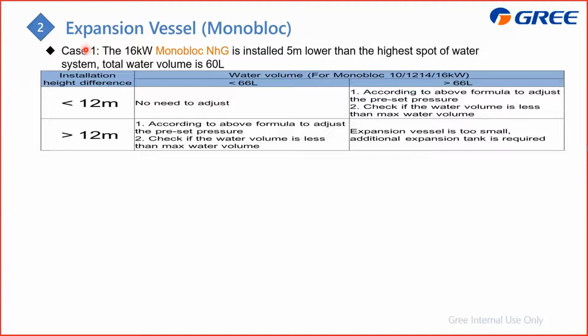So here is the detailed example. Case 1 is if you install a 16 kilowatt monoblock, and the water system is 5 meters lower than the highest spot of the water system, which means the outdoor unit is 5 meters lower than the highest point, and the total water volume is 60. According to this, you can find that if it is less than 66, which is this case, there is no need to install the preset, no need to adjust the preset pressure.